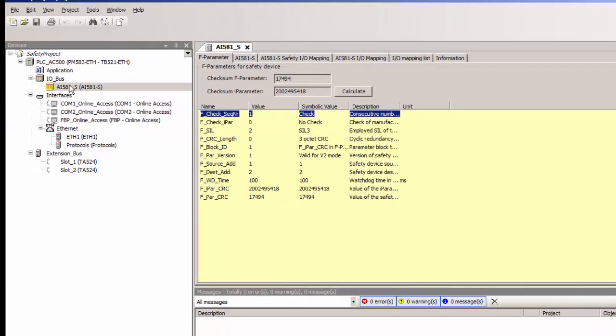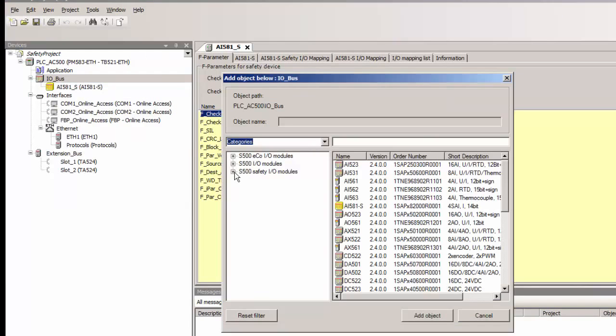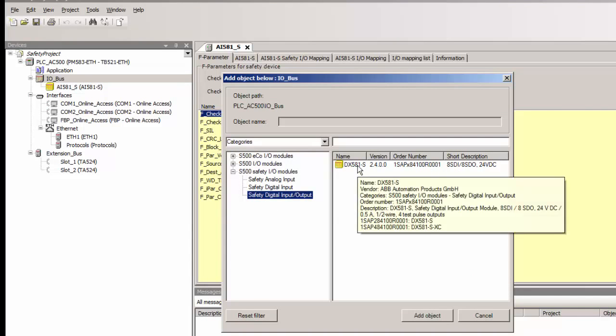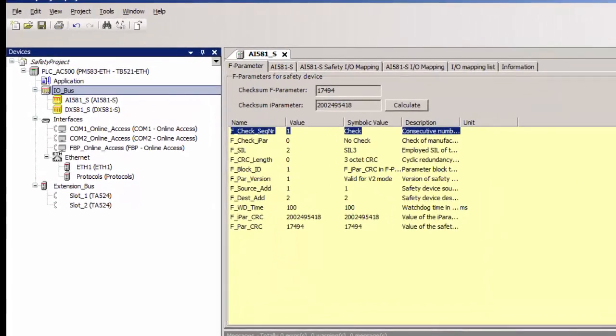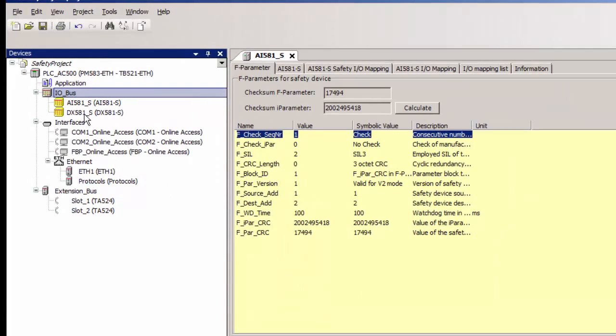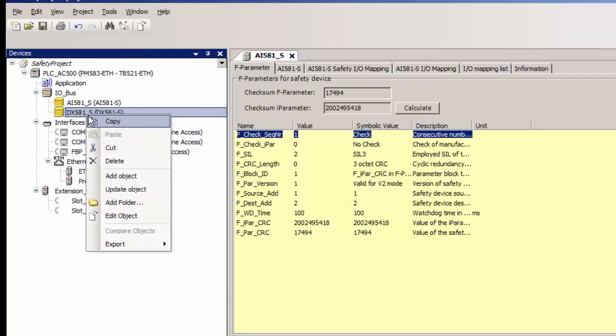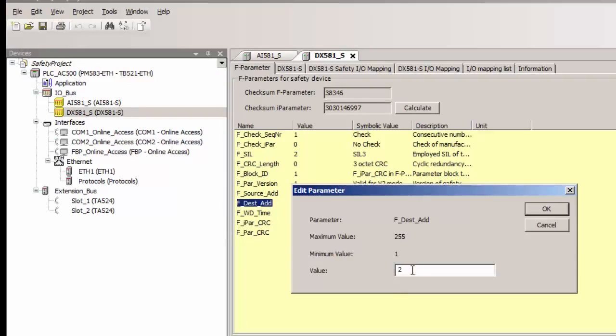Next we add the digital input output module DX581S and set its F destination address as 3. Every safety module needs to have a unique F destination address within a PROFIsafe island. Duplicate addresses would automatically be identified by the software and in such situation the project compilation will not be possible.